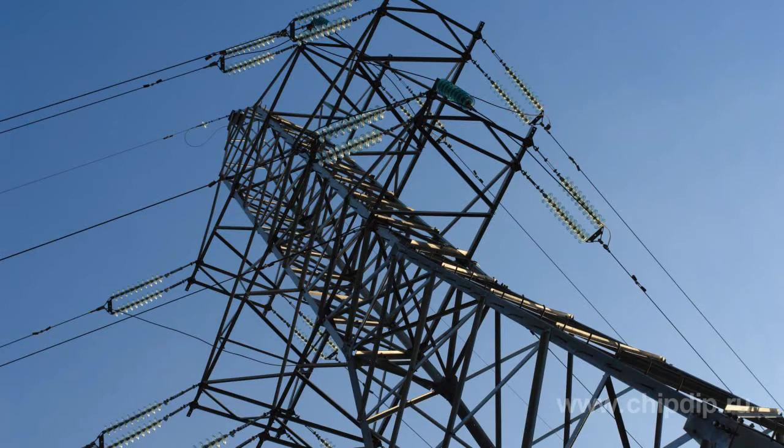A special cable runs over hot wires throughout the line, or at least near substations. It depends on the voltage of lines and the material of the supports. For example, lines of less than 20 kV are not equipped with these cables, and the main lines of 110 kV are protected throughout their length, regardless of the construction of their supports.